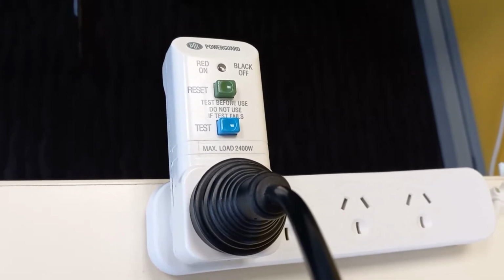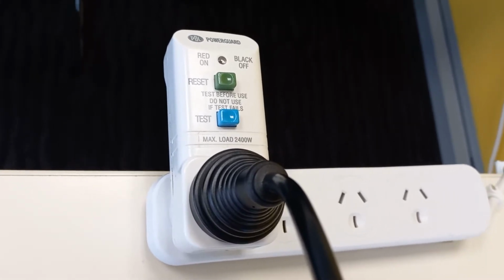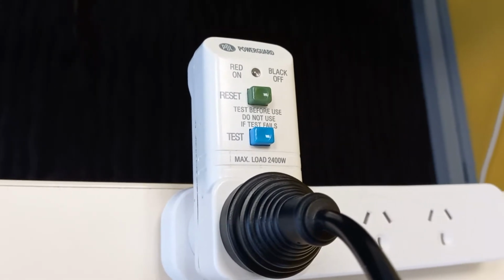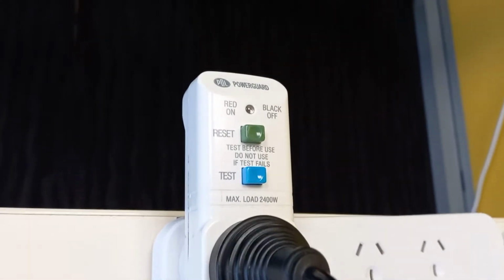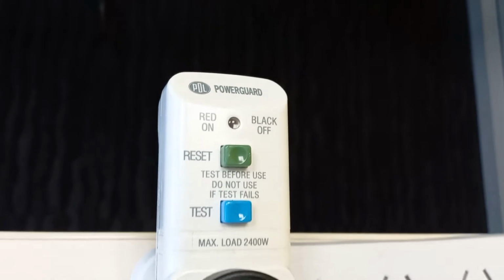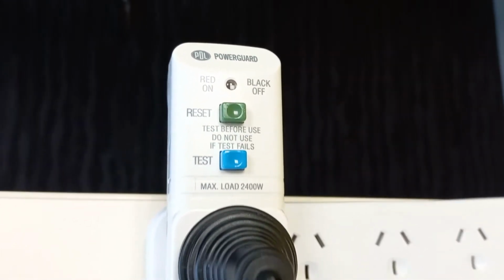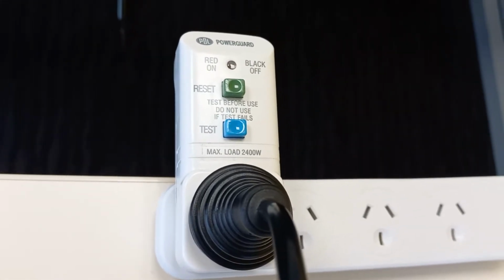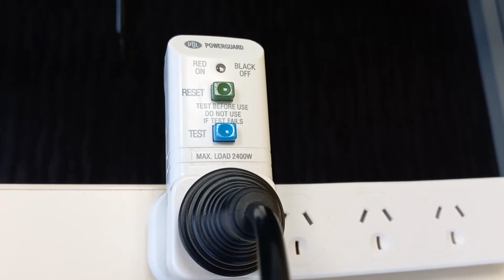We're going to test this residual current device, known as an RCD, sometimes referred to as a safety switch. It has a test button and a reset button, and for personal protection this is set for a sensitivity of 30 milliamps.